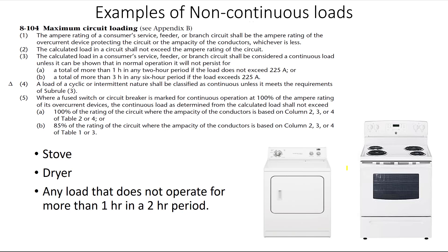Examples of non-continuous loads include your household dryer and your stove. Both operate with a timer and a thermostat that do not allow the equipment to constantly be heating the required area. Will a stove be operating for more than one hour in a two-hour period? No, it will not. Because we can prove that a stove meets the requirements of Subrule 3 — it will not operate for more than an hour in a two-hour period — it is considered to be a non-continuous load.